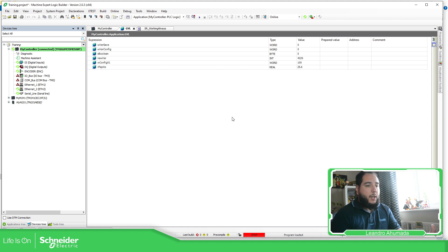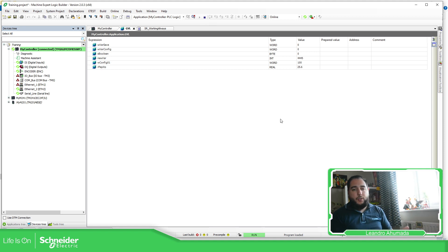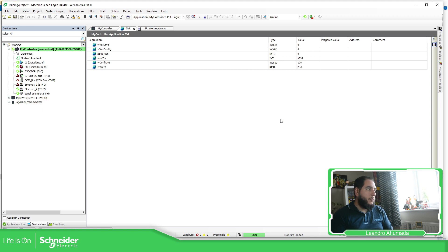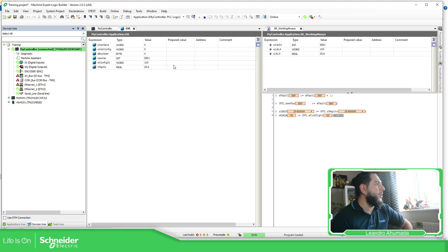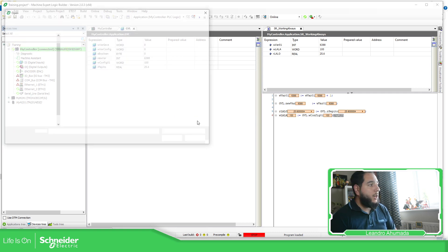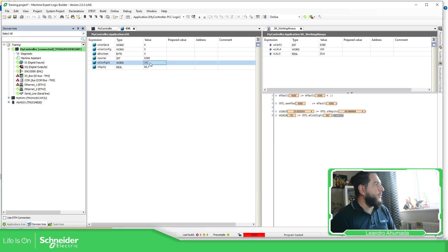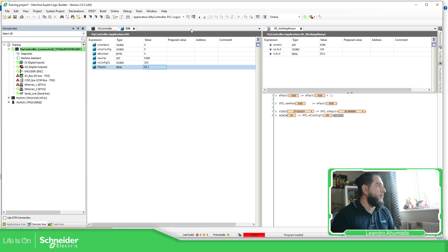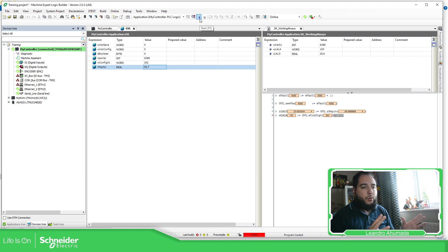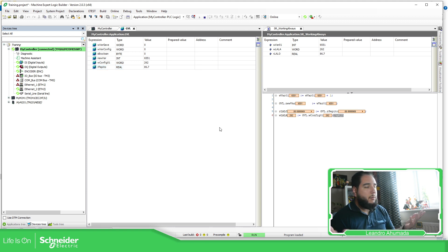Now, going back to the machine, I'm going to put it in run. Now I have my backup file — or the new configuration — in this CSV file. What I need to do now is stop the controller, then go again to Online, Advanced Configuration, Restore Data, and select the file that we want. You can see here I have the values 262 and 86.7. Now I make the PLC run again — and there we go, the new values are loaded.